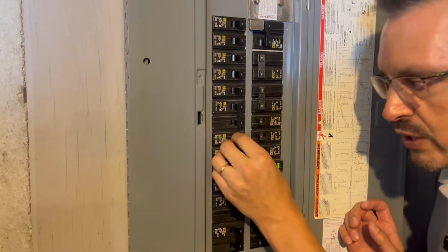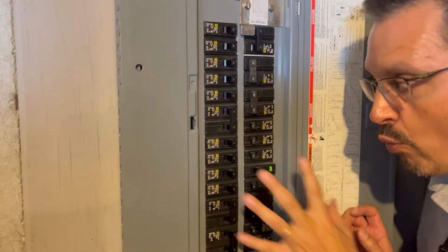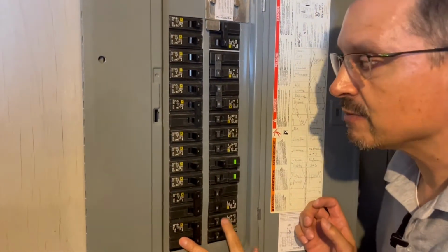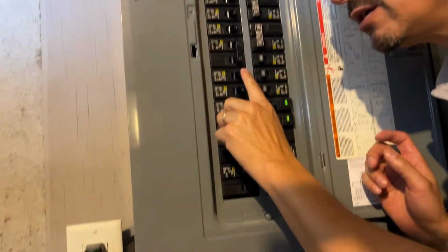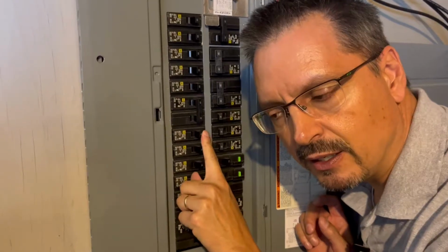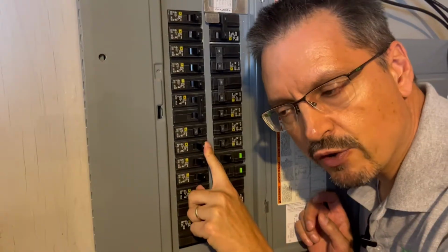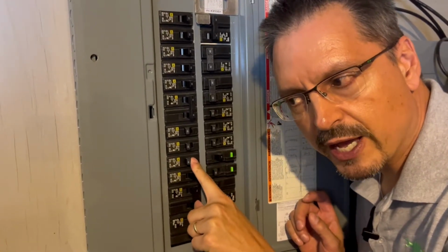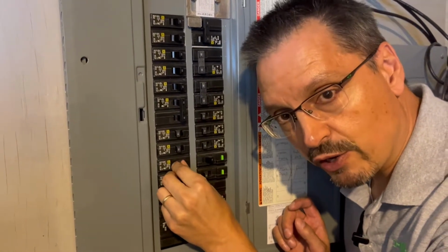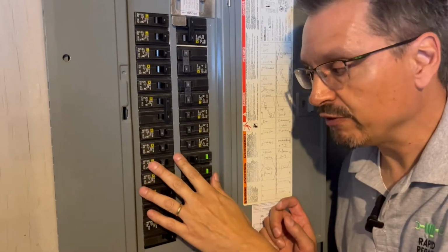One way to test which one it is, because you won't know right off the bat when you have a whole bank of them like this, is to start turning off circuits one at a time and listen. When you hear that sound stop, when you catch the right circuit, that's the circuit breaker that you need to replace. That's the one with the damage.